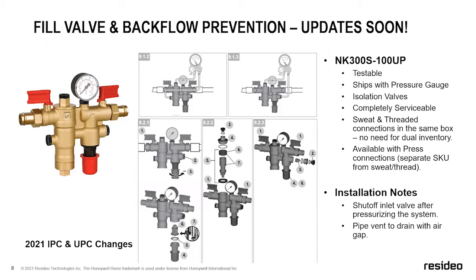The beauty of this is that think of this as your premium offering. We still offer a lower cost fill valve and backflow, but what this does is it offers serviceability. You can take every bit of this apart, clean it, put it back together. We ship it with a pressure gauge and isolation, so you can basically isolate it, fix it, clean it, put it back together, and get up and running. The number 1 killer for backflow preventers and fill valves on hydronic systems is sediment. So this is a big serviceability piece because you can actually get in and knock that sediment back out and put it together without having to replace it.